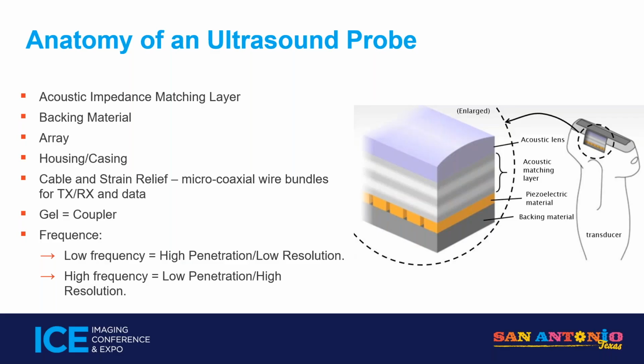Just keep in mind frequency has an effect on your image quality. Low frequency is low resolution. Your image is going to look worse, okay? But it's going to be able to penetrate more. So if you have a technically difficult patient, which is a large patient, and you're trying to image them, you're almost stuck having to use a low frequency probe, and that's going to cause problems with your image quality. So keep those in mind.